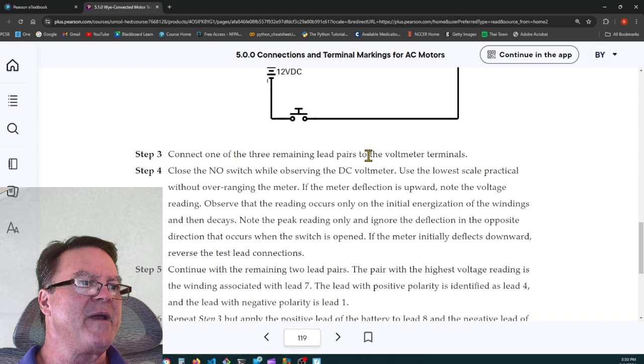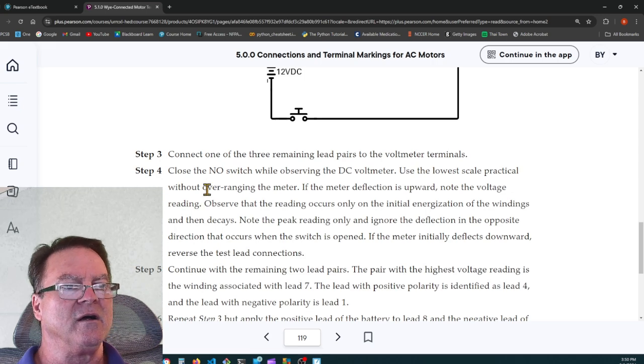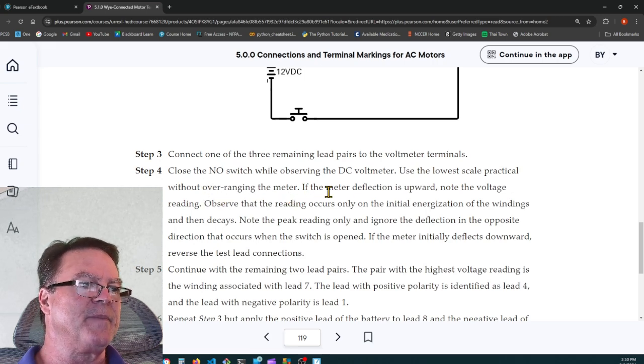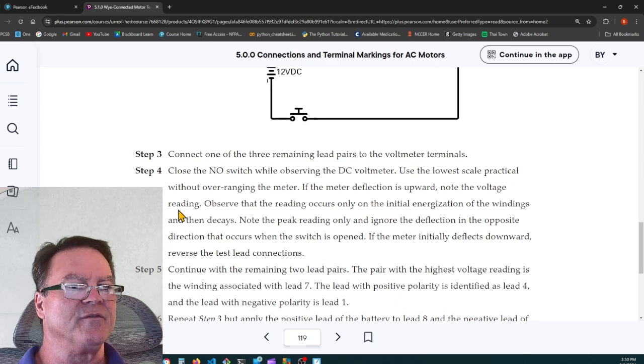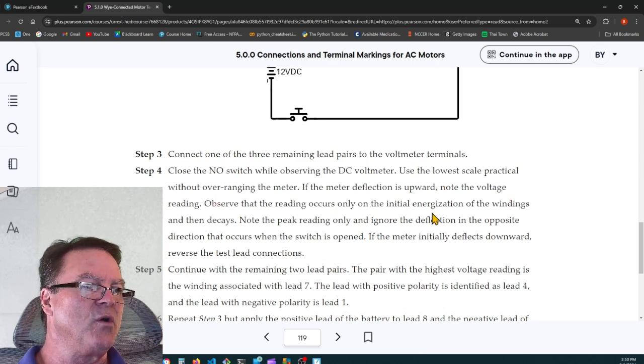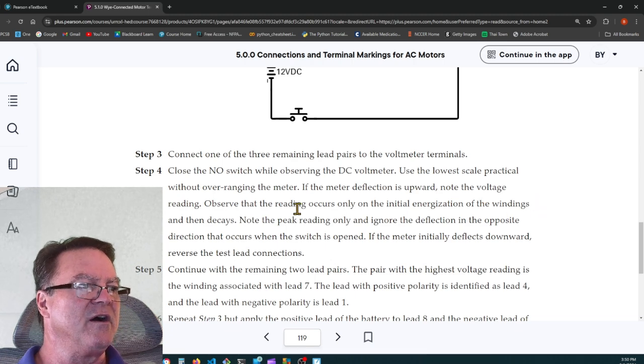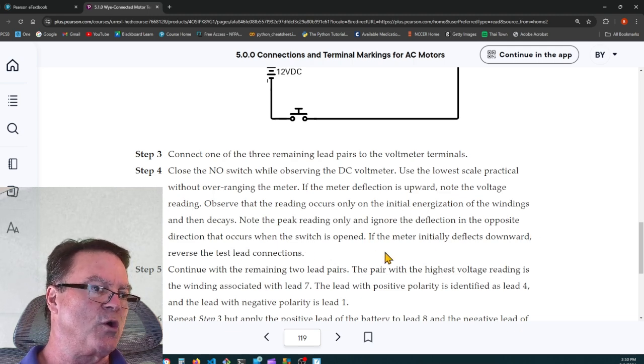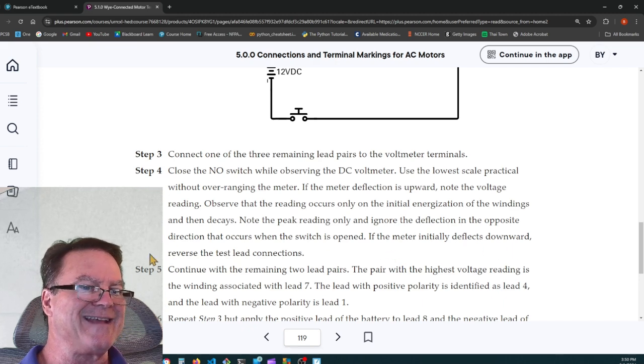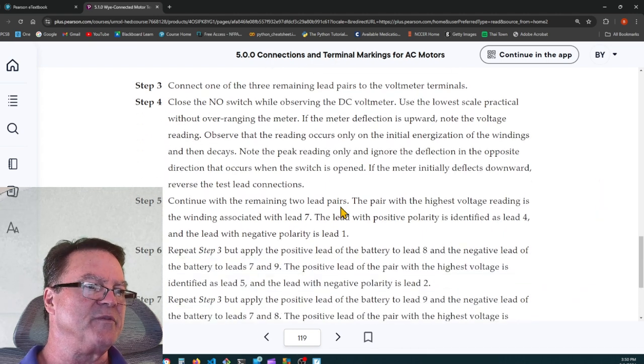It says connect one of the three remaining lead pairs to the voltmeter terminal. Close the normally open switch while observing the DC voltmeter. Use the lowest scale practical without overranging the meter. If the meter deflection is upward, note the voltage reading. Observe that the reading occurs only on the initial energization of the winding and then decays. Note the peak reading only and ignore the deflection in the opposite direction that occurs when the switch is opened. If the meter initially deflects downward, reverse the test leads and try it again. Continue with the remaining two lead pairs.